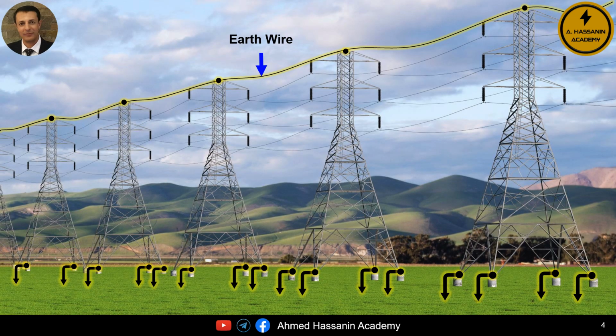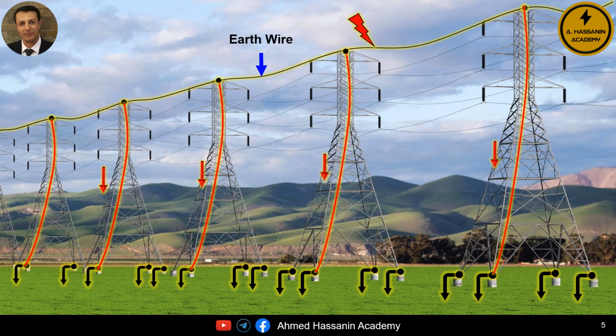Therefore, it is necessary to know that the tower body or the tower legs at the base are grounded using earth conductors or earth rods or a well-established grounding grid. From this, we understand that the earth conductor located at the highest point of the tower is well connected to the metallic body of the tower, and the tower body is connected at the base or grounded with a good grounding grid. Consequently, this ensures the easy and rapid discharge of any lightning strike to the ground.